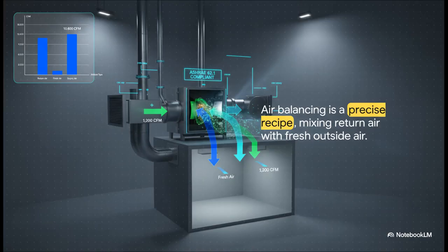This chart shows a really important concept called air balancing. The air being pumped into a room isn't just the same old air getting cooled over and over. It's more like a recipe. In this case, we're taking 10,800 cubic feet per minute of air from the room. We're mixing it with 1,200 CFM of fresh outside air, and that gives us our total supply of 12,000 CFM. This balancing act is what keeps the air from getting stale and meets critical ventilation codes like ASHRAE 62.1.